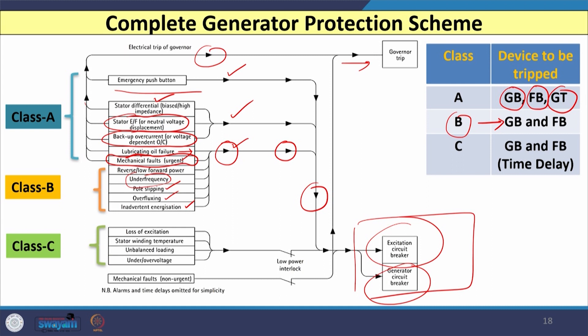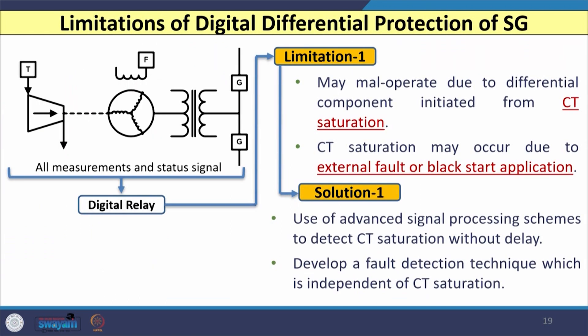Class C trip is initiated for conditions such as loss of excitation, stator winding temperature exceeding a limit, unbalanced loading, or under/over voltage situations. In this case, signals are given to the field breaker and generator breaker, but with some time delay.